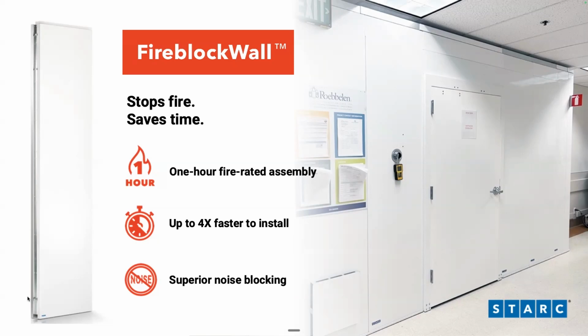And we specifically went through very rigorous E119 testing to make sure that this product adheres to the 1-hour fire code. But we also looked at all of the other parts and pieces. So FireBlock Wall also has a negative air panel. So we certified penetrations going through FireBlock Wall as well as our damper connections.